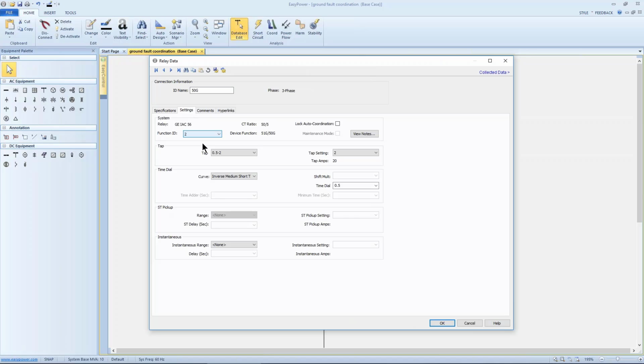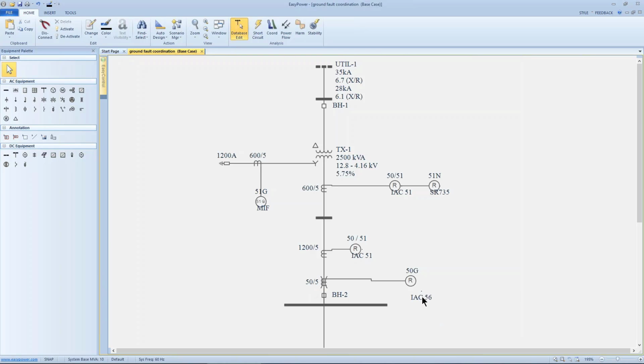As far as settings, again, we're going to set it at a relatively low level, and the sensitivity on the dial, or how long we'll tolerate that level of current, is a decision we make at the time we build the system. Most of the time, the relay at this level of protection, we really don't want to have instantaneous response. So let's see how this looks in the EasyPower TCC display.